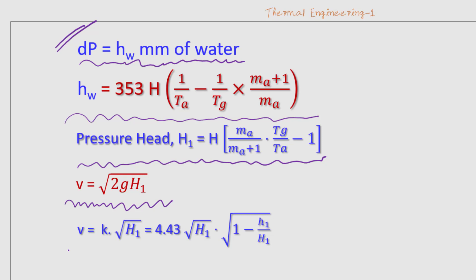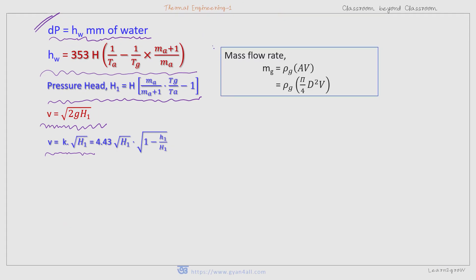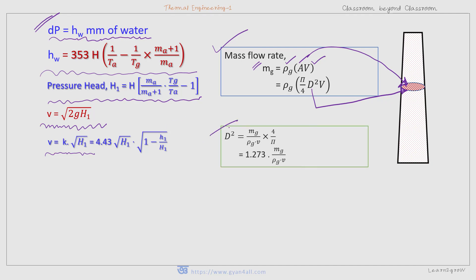But if there is any loss due to the material of the chimney, the formula is V equal to K into root over H1. For mass flow rate, the formula is mg — mass of gas flow — equal to rho_g, the density of gas inside the chimney, multiplied by A, the cross-sectional area of the chimney, and V, the velocity of flow. If A is the cross-sectional area, then D is the diameter of the cross-section, and we can find the diameter of the chimney using this formula.